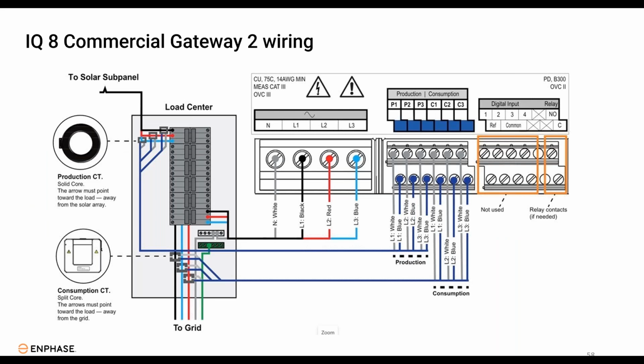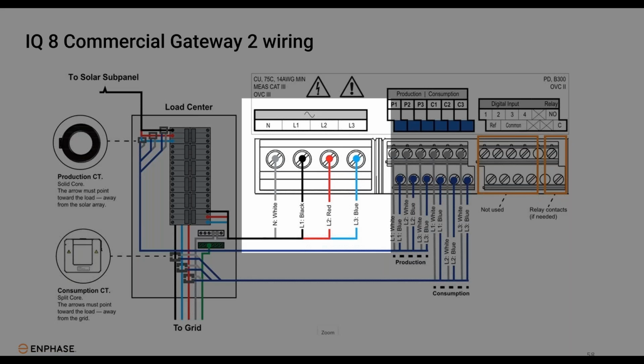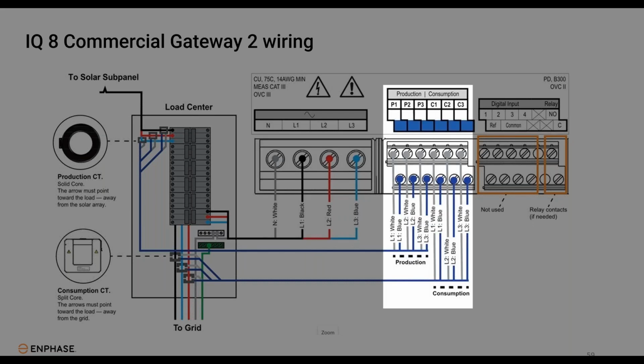When wiring the commercial gateway, you're only going to be using 2 terminal blocks on the gateway. The one on the left is to power the block, and you'll wire 3 phases and a neutral into it. The block on the right is for the CT wiring. The 3 production CTs will wire into the first 3 ports. From left to right, you'll start with line 1 to line 3.